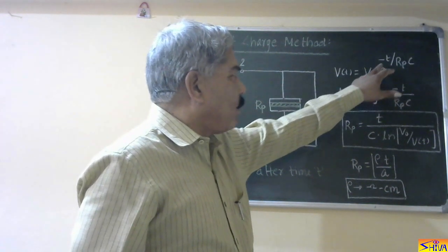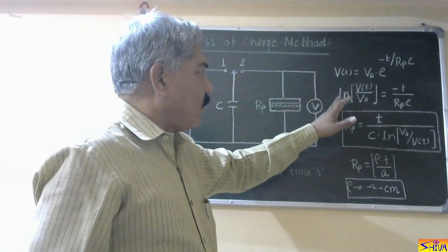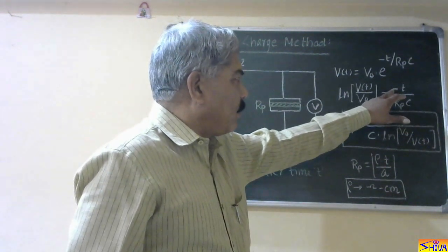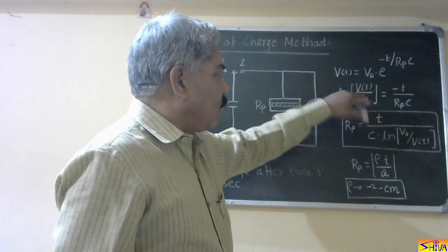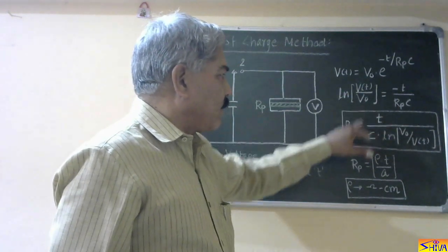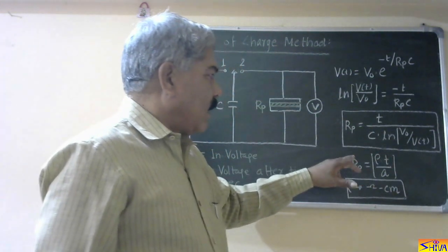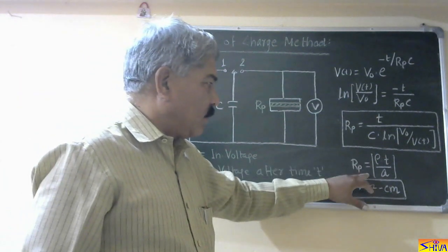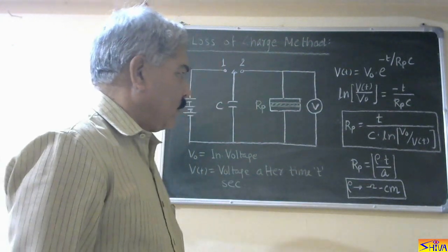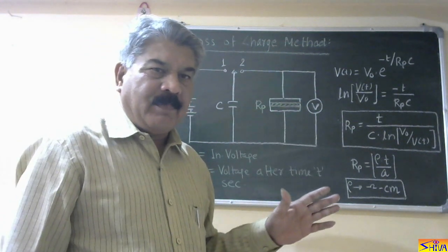The formula for capacitor voltage is: Vt equals V0 times e to the power minus T upon Rp times C, where C is the capacitance. Taking the natural log and rearranging, we get Rp equals T upon C times ln(V0 upon Vt). If we want to find volume resistivity, we use Rp equals rho times t upon A, where volume resistivity is measured in ohm-centimeters. In this way, we measure insulation resistance or DC resistivity by the loss of charge method.